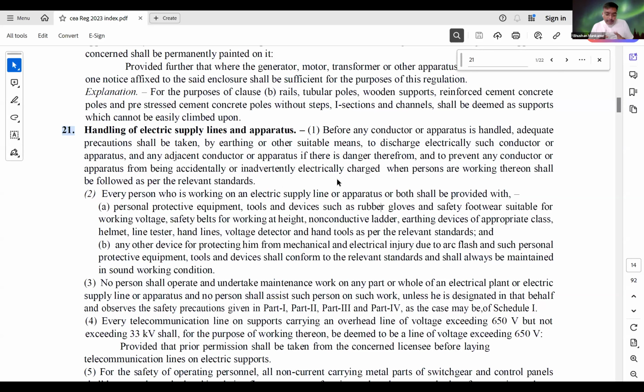Ideally, suppose I am on pole 21 and some maintenance activity has to be taken care of. The conductor toward the next pole should be earthed suitably, so that the electrical charge from the other side is isolated before it can enter the person who is doing maintenance. And the conductor from behind should also be earthed. So both sides where maintenance is to be done should be earthed properly to avoid danger to the person doing maintenance.